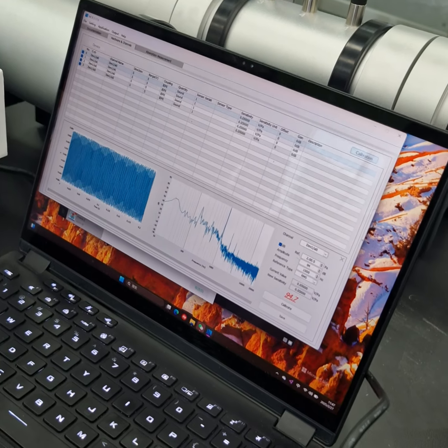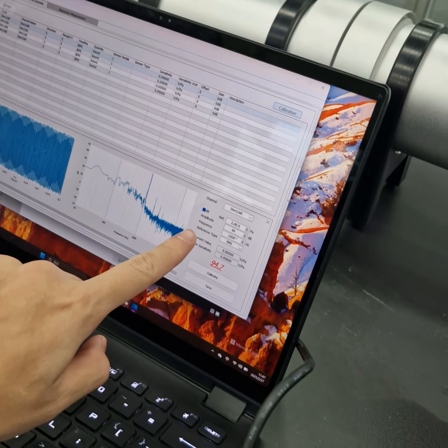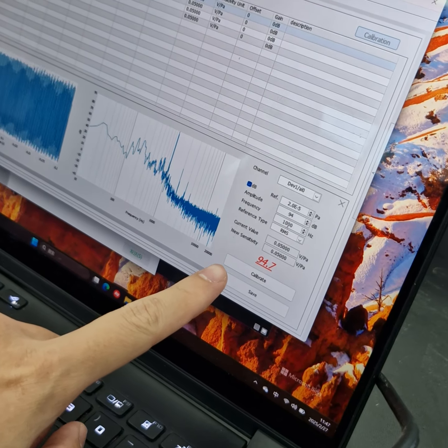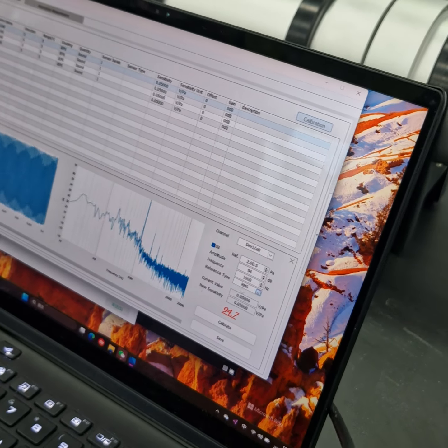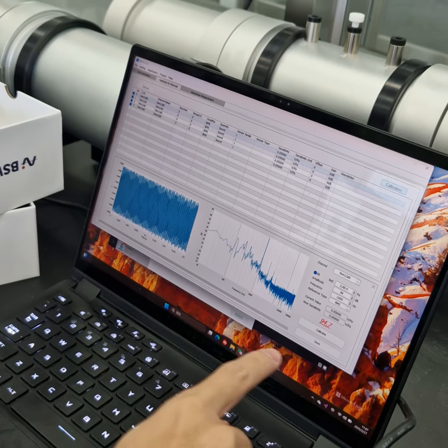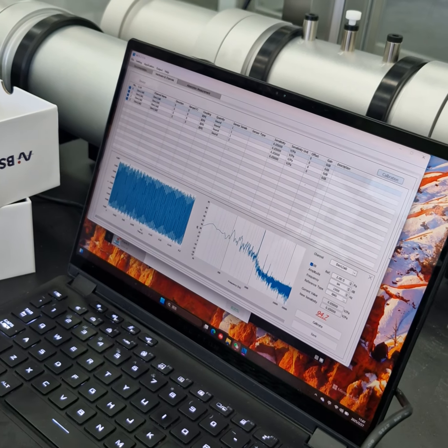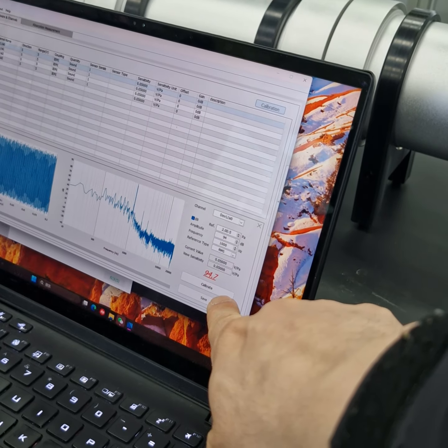94 decibel is generating here. You can see the amplitude is 94 decibel and 1000 hertz. Usually you don't need to change this. As you can see, the response is 94.7, which is different from what it's generating.